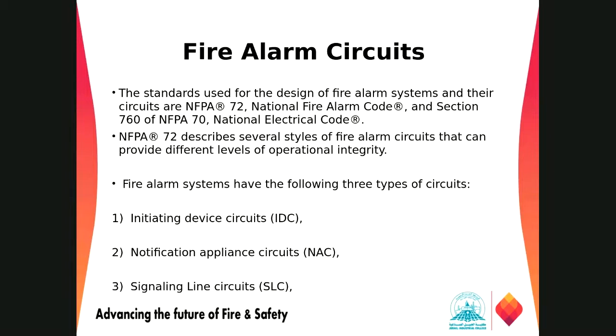It transmits data in a two-way direction, so if there is a fire, it will let us know the exact location of the fire. So SLC is mostly for addressable fire alarm systems. Normally we have conventional, we have addressable, and we have the addressable intelligent system.